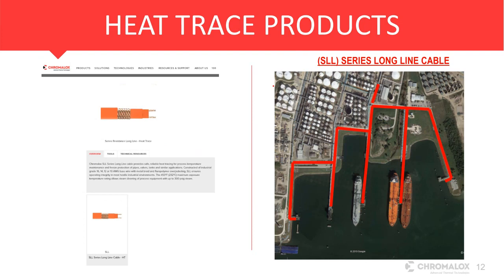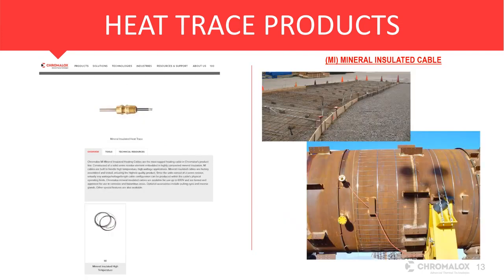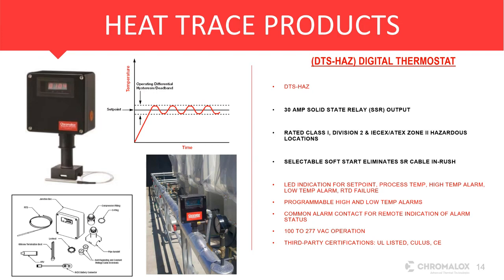A couple more quick things before we get to the tour. We have a unique product known as our DTS product line. Of course, we have MI cable as well. Apologize, got ahead of myself. So we certainly have a full line of MI cable. Getting to this DTS, this unit is kind of unique to Chromalox. You actually have a numeric temperature indication on the front of the box. It is Class 1 Div 2 for all your installation areas, and it comes with a 30 amp SSR solid state relay integral to the unit.